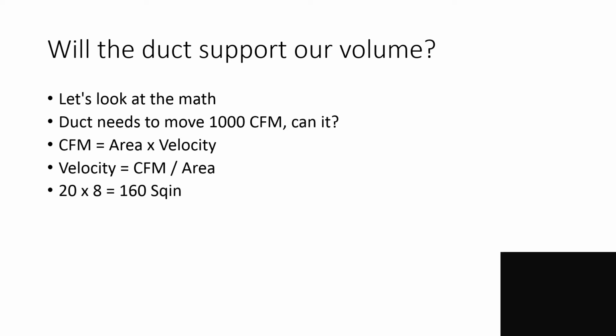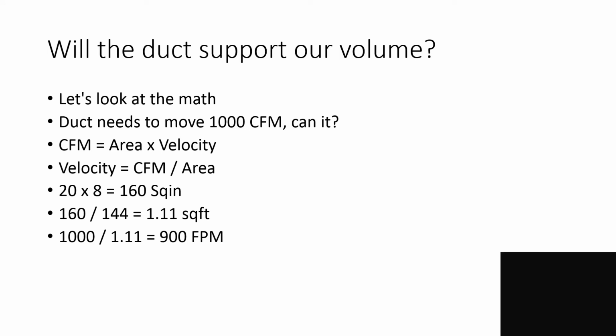Our ductwork at 20x8 would be 160 square inches, and that area does not recognize square inches. In the CFM formula, that area up there is in square feet. So our 160 square inches gets converted into square feet by dividing it by 144. So we're going to solve for feet per minute by taking our 1,000 CFM and dividing it by 1.11, and it's actually some more ones, but doesn't matter.